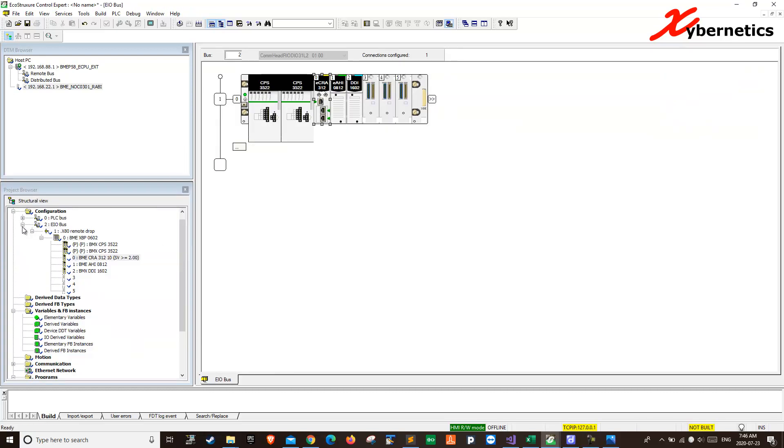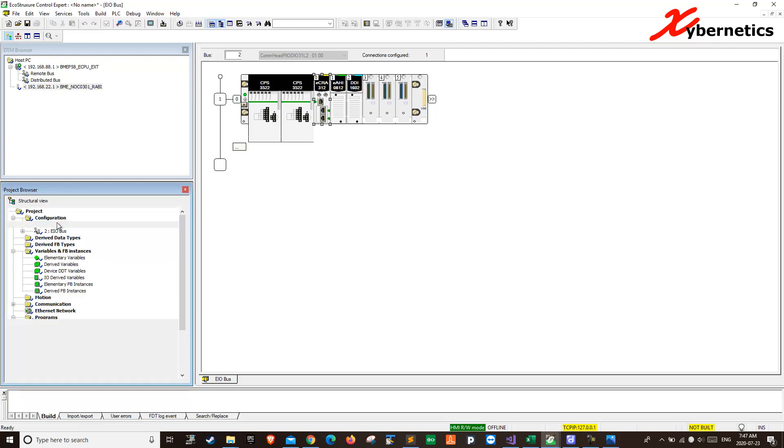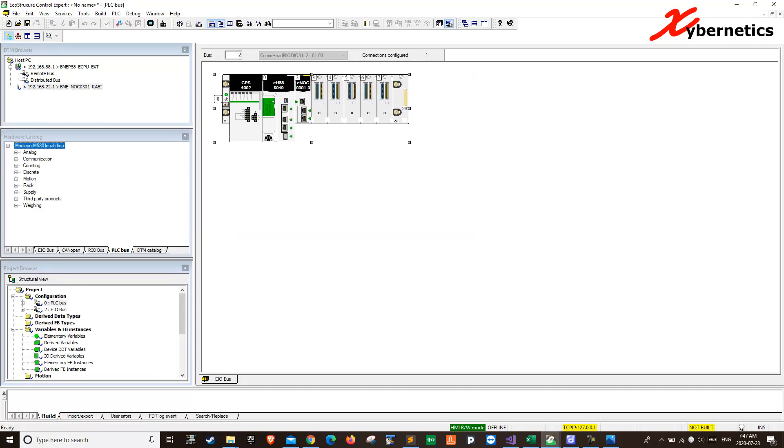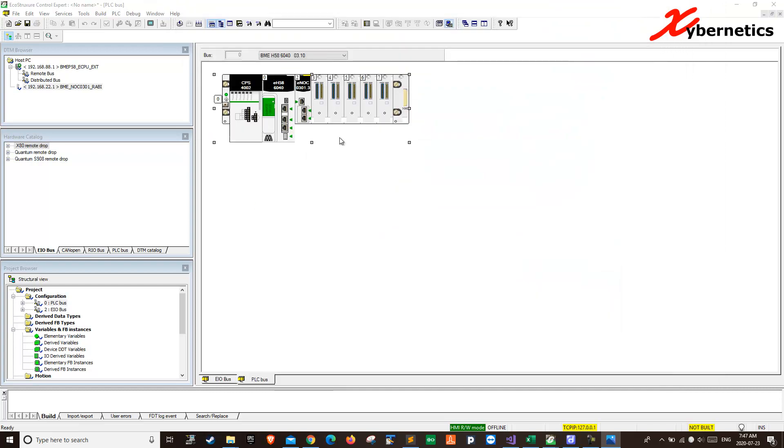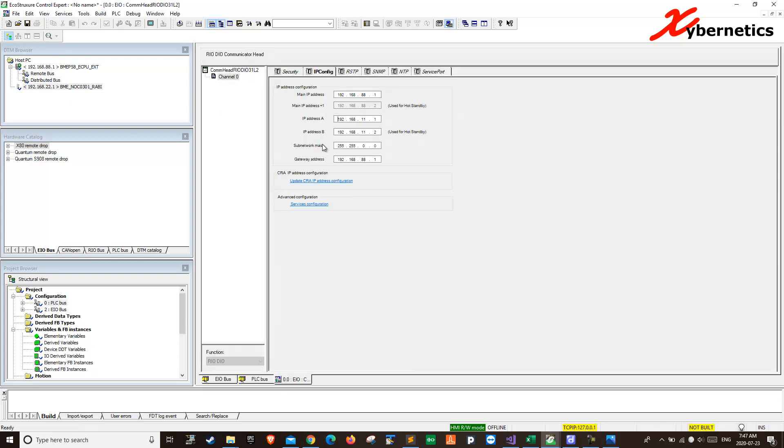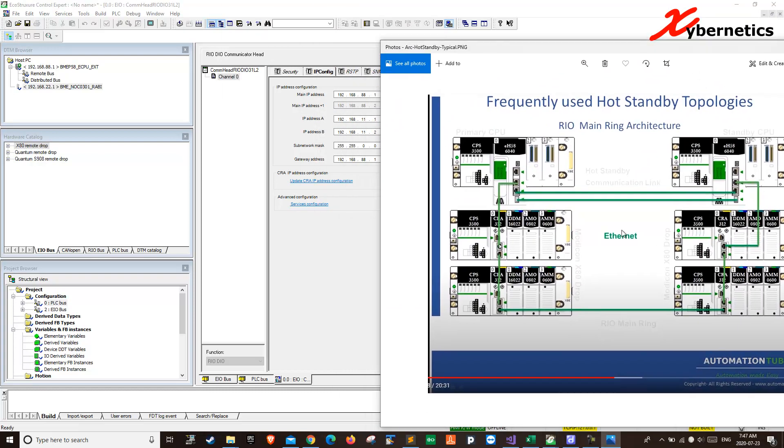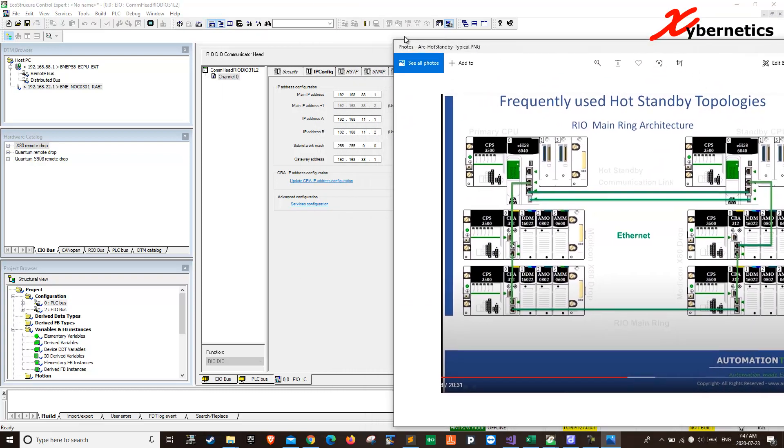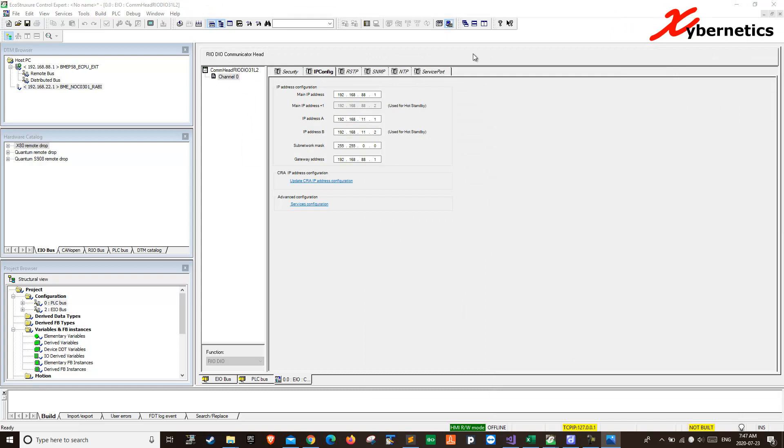So it comes from the main CPU itself. So if I go back to my main CPU and I say main CPU, I'm talking about this guy here. This guy actually has a DHCP server, which distribute an IP address for that particular CRA or remote NIC card. So, the change to manage that IP address, you double click this guy here again. And you'll notice that, the, okay, let me show you what I mean by here. So your service or your main Ethernet jack here, this IP address is 88.1 and IP address for A and B is here. So since this is connected, it's going to be connected to this guy here, naturally it'll follow 192.168.11 subnet altogether.